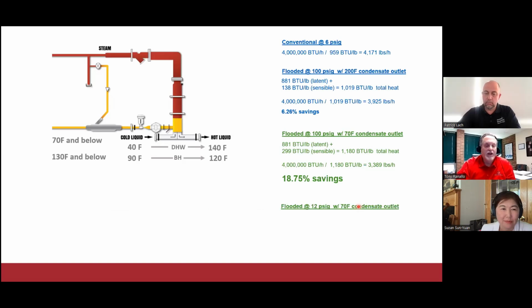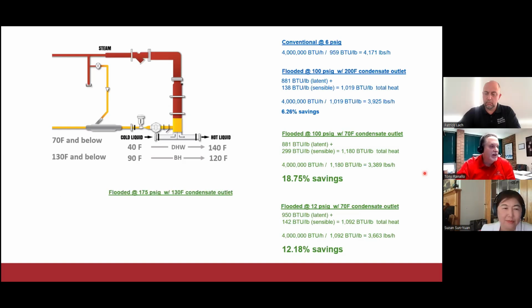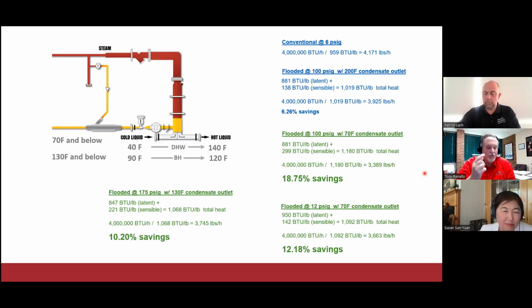Now, say we only have 12 PSI steam, maybe it's a low pressure system, or we have to be after the PRV stations that are in there for other equipment. We can still give you about a 12.18% savings. So there are a lot of advantages to using this type of heat exchanger. In fact, this one's very interesting because we can take 175 PSI steam, and if we are looking at a very low temperature building loop hydronic temperature, in that 90 to 120 range, we can now reduce our condensate to 130 and you can still recover about 10% in savings. So this is all important. When we get to some slides down the road, we will have to keep these in mind.